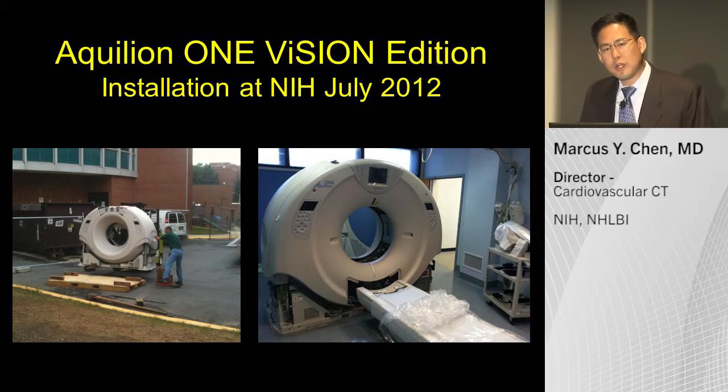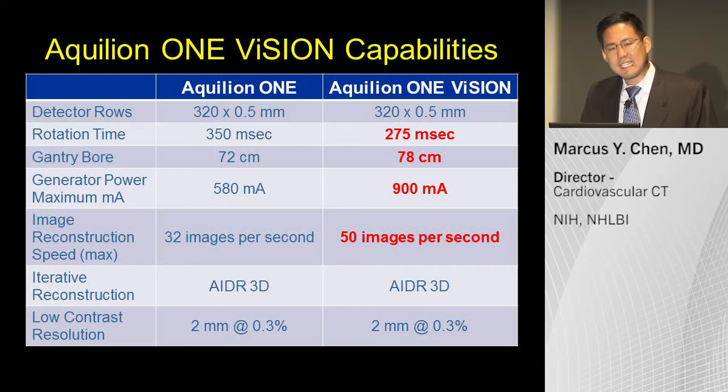How does the Aquilion One Vision Edition differ from the original Aquilion One? They're both 320-detector scanners, but the gantry rotation time is now faster at 275 milliseconds versus 350 on the original system. The gantry bore is larger at 78 centimeters versus 72 centimeters. The X-ray generator has been enhanced — the scanner can now produce 900 maximum mA versus 580 previously. Images are now reconstructed at 50 images per second.